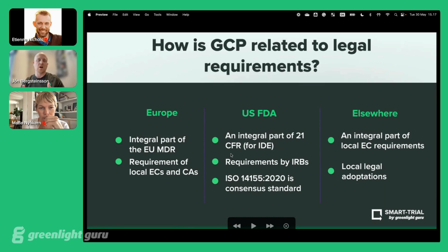And then what FDA also has done is that they've categorized the new ISO as a consensus standard, which means if you ensure that you document your clinical activities according to that standard, you can partly fulfill the CFR 21 requirements. However, US FDA does have some additional US specific requirements related to good clinical practice that you also need to make sure that you cover. So you always have to make sure that if you're following ISO 14155 for a multi-center global study, that the US specific good clinical practice requirements are taken care of, because they're not automatically taken care of by the ISO 14155. This might be as little as just making sure that documents are named correctly in specific ways and that you have appropriate agreements in place.